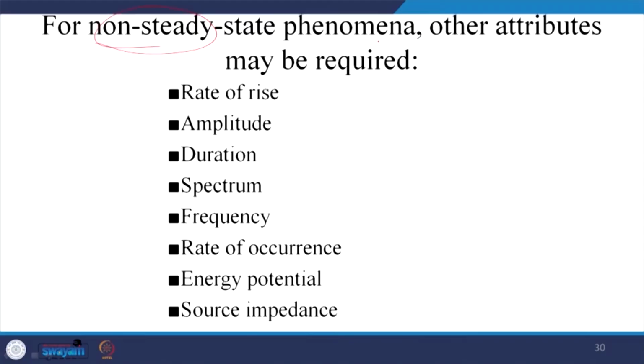And there are other power quality issues related to non-steady state phenomena and other attributes, mainly transients. So, the rate of rise, once you are charging a capacitor, the rate of rise of its amplitude, duration, spectrum, frequency, rate of occurrence, like you may have a notch here, and after 5 cycles there will be another notch. So that is the rate of occurrence, and its energy potential: how much energy is associated with it. We need to see that too. Essentially it may be a very high voltage spike, but the duration is very small, so the energy potential is less. In the same way, the source impedance also plays an important role in the rise time of these devices.